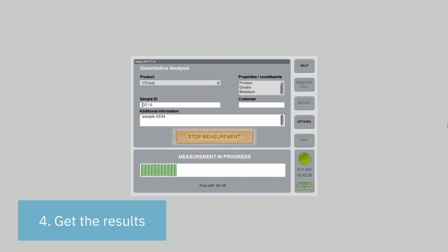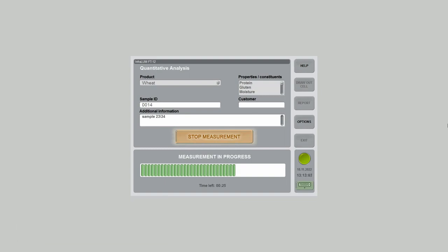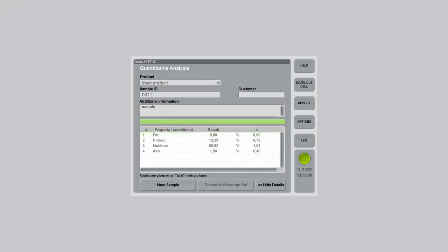Fourier Transform NIR spectrometry ensures that Infralum FT-12 performs a precise and consistent reproducible analysis. For example, relative error for fat in meat analysis is 1%. For protein in wheat, it is 0.5%. And for the fat content in milk, it is 0.04%.